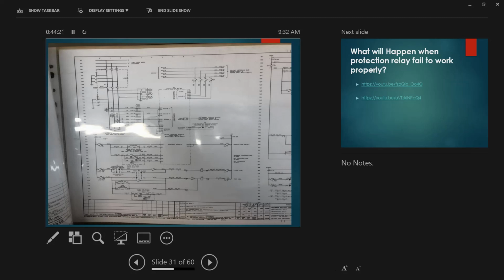So we must always keep in mind, especially as protection engineers, that we don't forget the breaker failure. Yeah. So breaker failure means if you have an instantaneous trip and there is no signal coming from the breaker that it already tripped, the relay looks like the coil has failed. So it needs to do something to cut off the power upstream because the relay is waiting for the breaker to feed it some inputs.